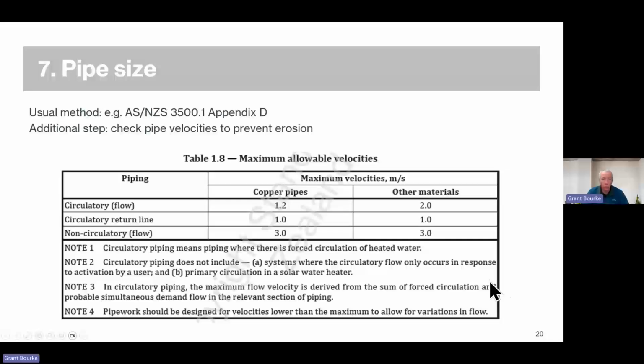So for the return pipe, we're obviously just working out what the pump's pumping the water around at. In the supply pipes, we're going to add the flow rate that the ring main pump is causing, plus the normal simultaneous demand in the supply pipes. So in summary, same as what you always do, but you need to just check your pipe velocity so you're not going to wear the copper out.